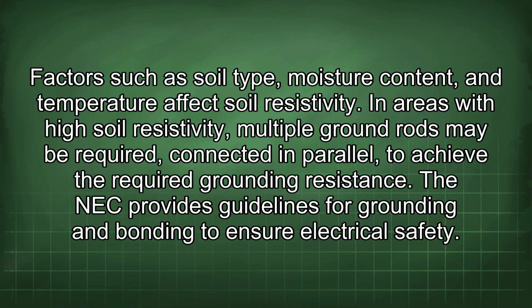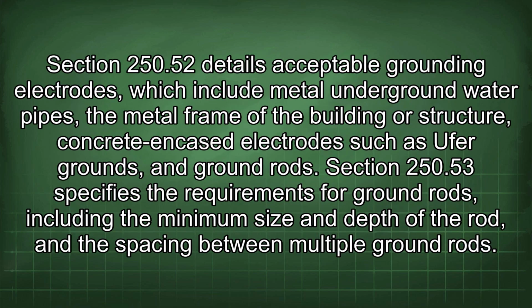The NEC provides guidelines for grounding and bonding to ensure electrical safety. Section 250.52 details acceptable grounding electrodes, which include metal underground water pipes, the metal frame of the building or structure, concrete encased electrodes such as Ufer grounds, and ground rods. Section 250.53 specifies the requirements for ground rods, including the minimum size and depth of the rod, and the spacing between multiple ground rods.